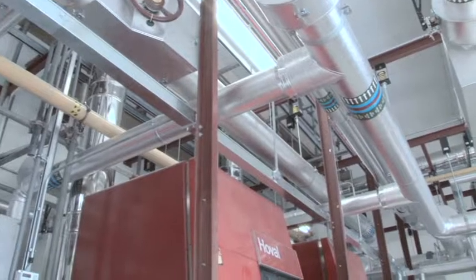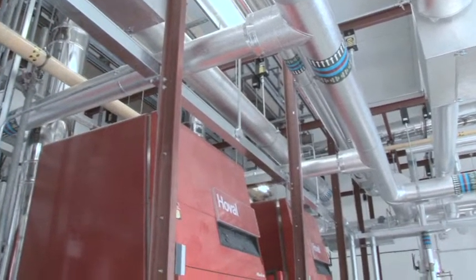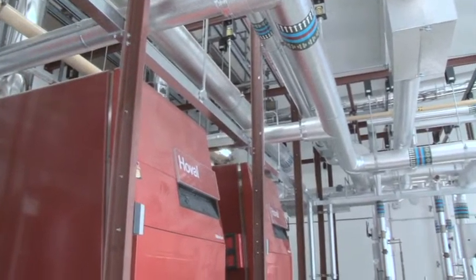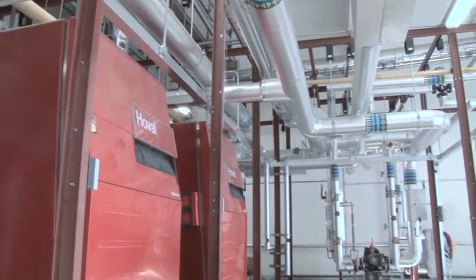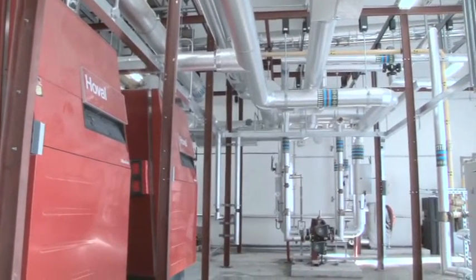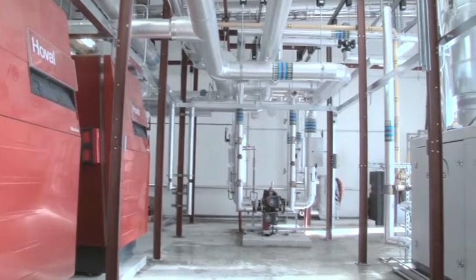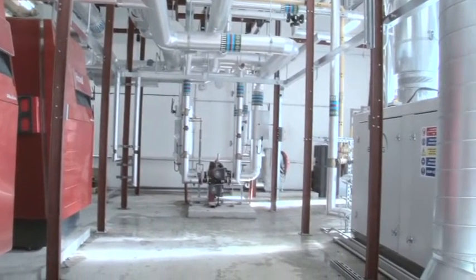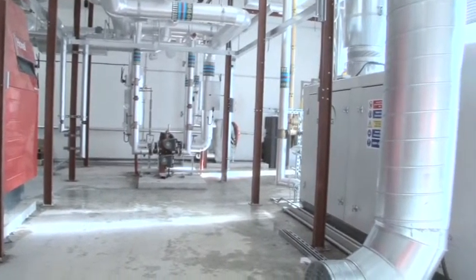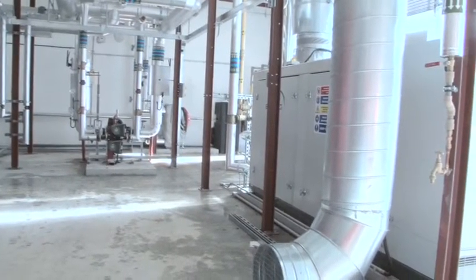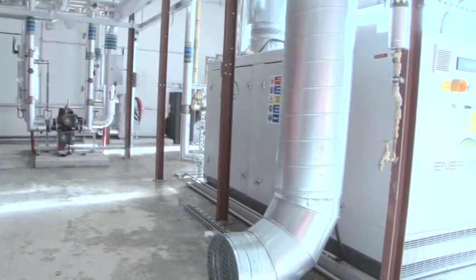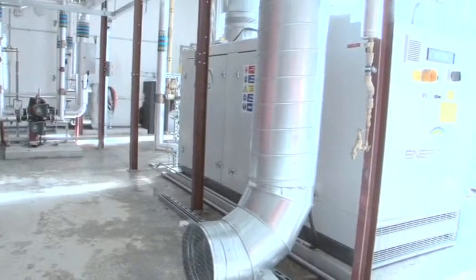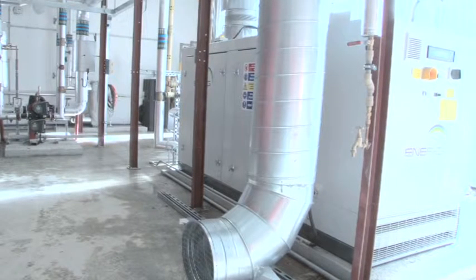Okay, so what we're looking at here is the main plant room energy centre that we've been talking about that's going to provide all the heating around to all the flats on the site here. And what we're looking at the moment is the combined heat and power system, the CHP unit. This basically is acting as the lead boiler in the system, provides both heat and electricity.